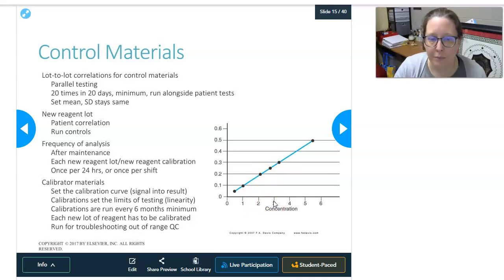And so calibrations will set the limits of testing, so you can also use them to determine the linearity. As long as this calibration line is linear, is straight, then you're in a good analytical measurement range. Once it starts straying, flattening out or curving somehow, then you're out of linear. You can't be on that level, that concentration, that absorbance. You can't report out any kind of results. And if you had a result that was too high to read, you would have to dilute it so that it would read within the linearity.